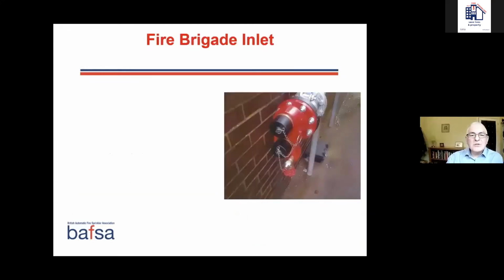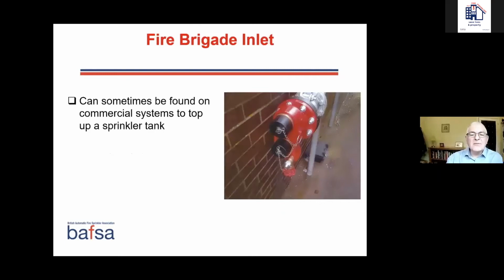Something I thought I'd slot in here when talking of firefighting, and it's something I've come across more than once in recent times, is this inlet valve. You can sometimes find one of these valves at large buildings that's actually connected to the sprinkler tank. It's interesting how many times people are confused as to what that valve's supposed to do. That valve is for topping up the sprinkler tank, and certainly not for taking water out of it.